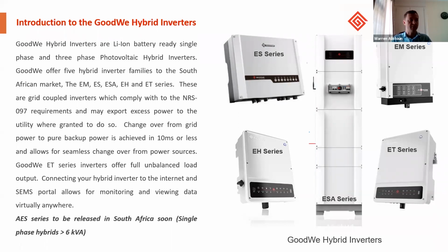The GoodWe hybrid inverters have a transfer switch of 10 milliseconds or less. So when the grid fails, there's a seamless transfer of power sources. Another great aspect about the GoodWe inverters is the full unbalanced load, with the three-phase series being the ET series. Connecting your inverter to the internet allows for viewing of the data and remote configuration virtually anywhere in the world, as long as you have an internet connection. Something worth noting is the AES series should be released in South Africa in the future, which will be hybrids greater than 6 kVA.